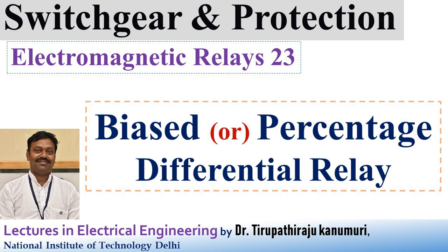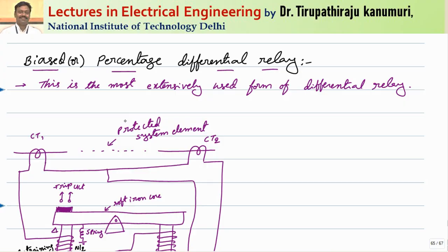Today we are going to discuss the biased or percentage differential relay. In the last class, we saw the basic differential relay. The basic disadvantage is that it will trip due to imbalances in CT secondary ratios caused by constructional differences — both CTs saturate at different fault current levels, causing unequal secondary currents even for external faults, making the relay operate incorrectly. The better option is the biased or percentage differential relay.